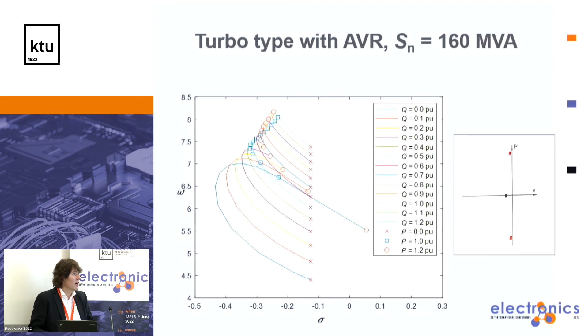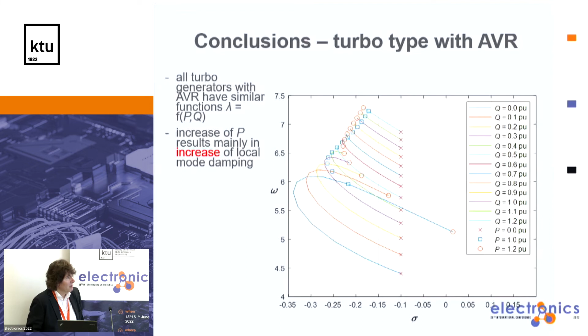And the conclusions are, again, the dependency of eigenvalues is similar by all analyzed generators. Increase of P results mainly in increase of local damping, only in special cases going far into the unstable plane. Increase of Q means increase of frequency. The stability high problematic area is when we have an extreme high value of P, and the stability low problematic area is when we have low P and low Q. These are very important conclusions.